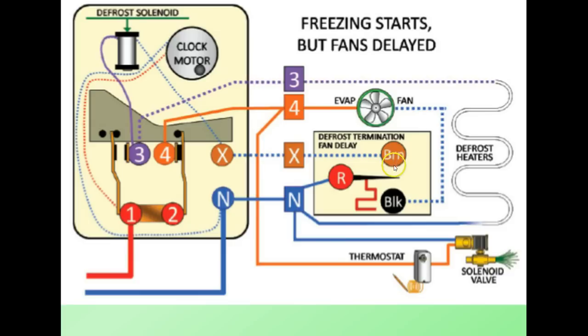For the time it takes for the coil to get from its defrost temperature down to its operating temperature, this contact is in limbo and is not made. So there's a little bit of a time delay before this contact makes, which delays the starting of this fan.